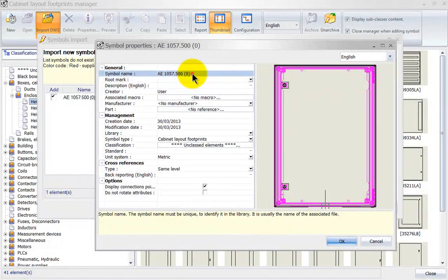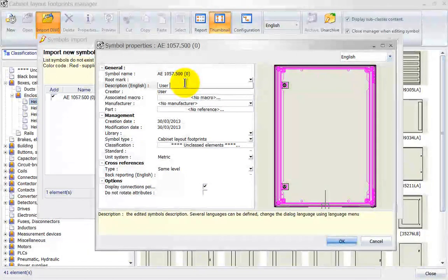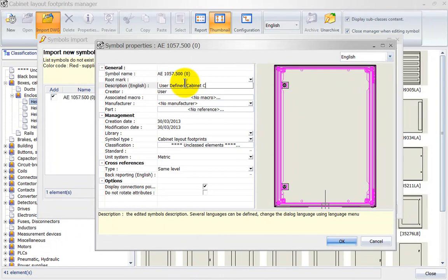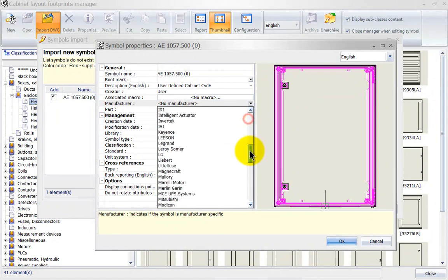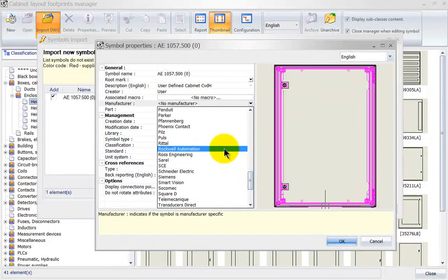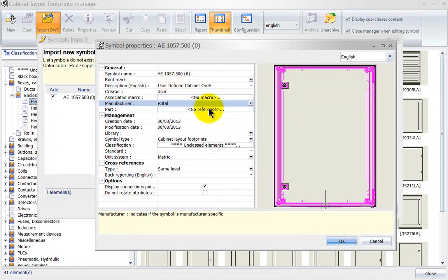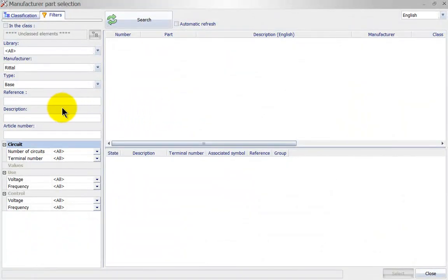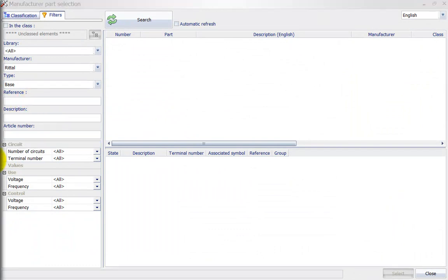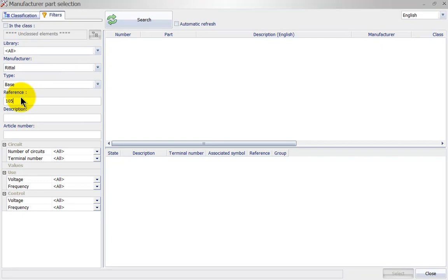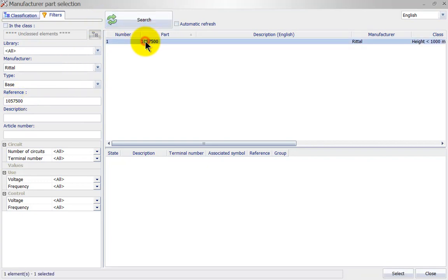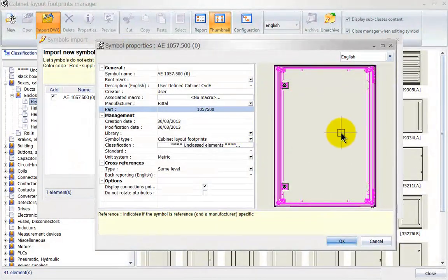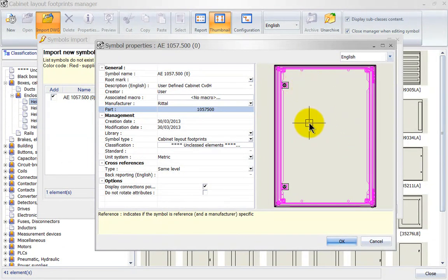I can specify a description here. As I always say, it's good to add as much information as possible because it's very easy to filter on this data, and we can immediately associate it to a manufacturer's part as well. I know the manufacturer's reference number, which was 1057500, and this will associate the manufacturer's part to this symbol. So the next time I right-click and insert the symbol it will automatically insert this 2D footprint. Click OK.